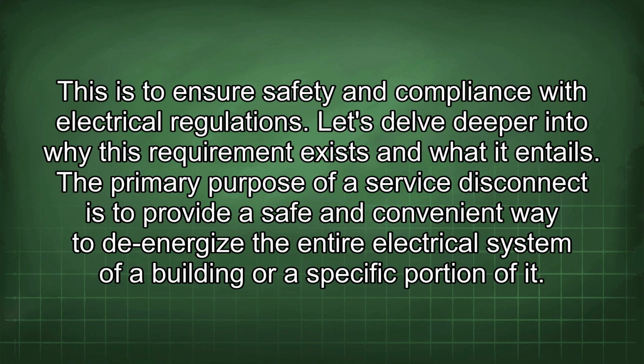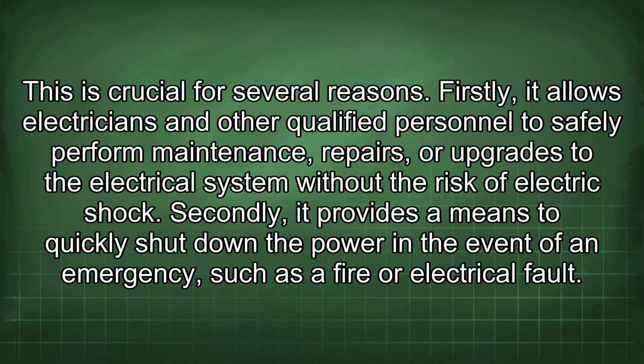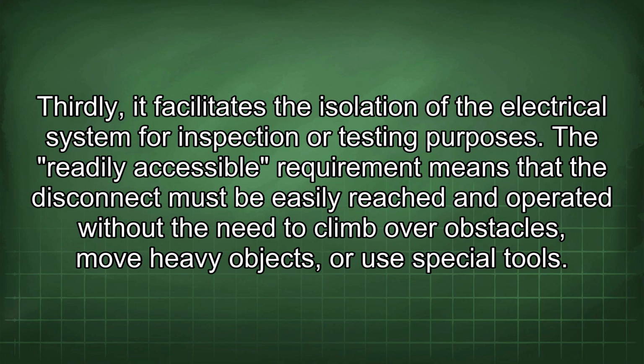The primary purpose of a service disconnect is to provide a safe and convenient way to de-energize the entire electrical system of a building or a specific portion of it. This is crucial for several reasons. Firstly, it allows electricians and other qualified personnel to safely perform maintenance, repairs, or upgrades to the electrical system without the risk of electric shock. Secondly, it provides a means to quickly shut down the power in the event of an emergency, such as a fire or electrical fault. Thirdly, it facilitates the isolation of the electrical system for inspection or testing purposes.